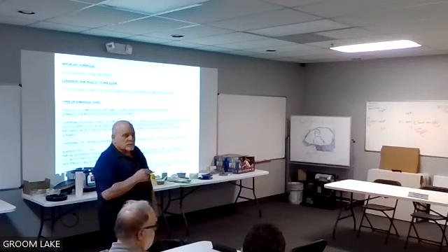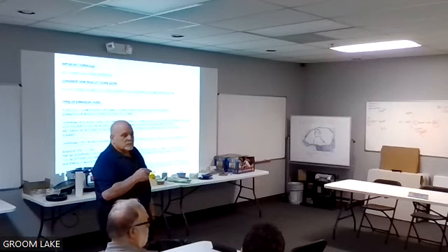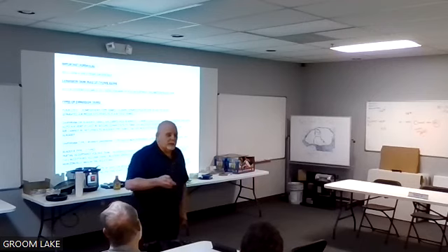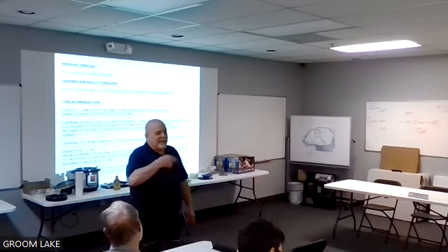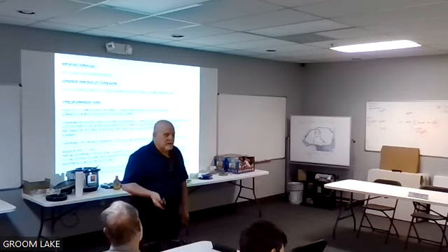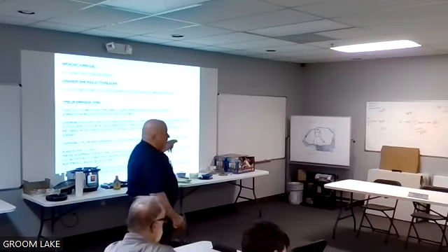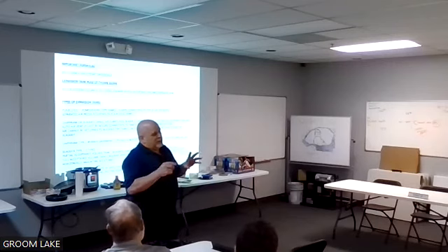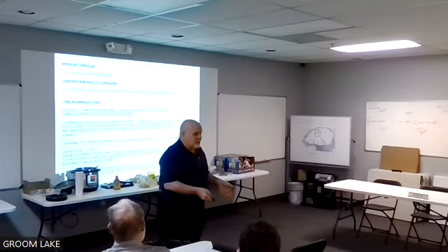Question on the expansion tank rule of thumb: the total volume of a full acceptance volume expansion tank, is that in cubic feet or gallons? Well, it's liters or gallons. I'm like a Taco rep, but they all use liters. Like a CA 450, that's 450 liters. And that is the full volume of the tank. Where if you get into the CBXs or the CXs, which are the diaphragm, you actually have to look up and say it'll hold 18 gallons of acceptance, but it's a 46-gallon tank.